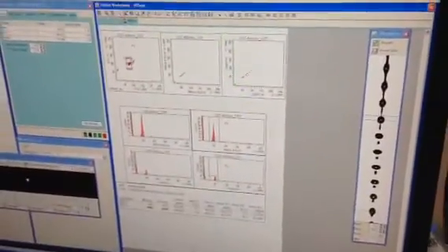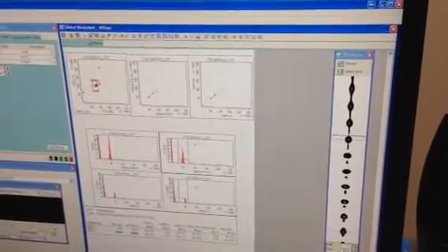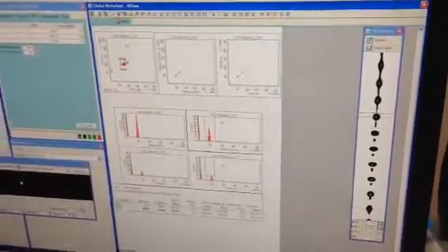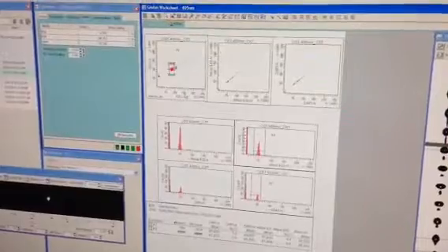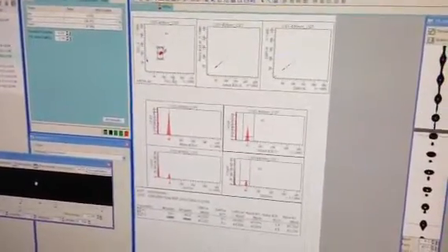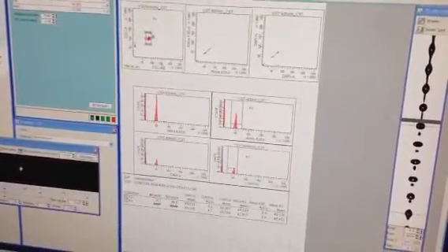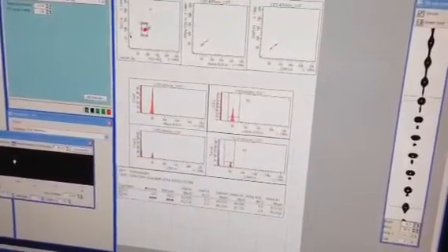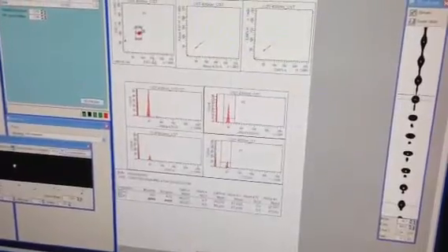So if the window extension is changed to 0, and we suddenly lose signal or the signal drops, we know that the laser delay is not set optimally for the bead or particle itself to be in the center of the window. So we would adjust our laser delay at this point to have the signal maximized at the 0 window extension, so that when we open up the window extension, we'll be seeing a complete signal very clearly and consistently. But by maximized, you mean at our target, which is 15? Yeah. Whatever we had previously set as our standard measuring point, we want that to be maintained every time. So it should not drop when you hit window extension 0. No, changing the window extension shouldn't cause that signal to drop if the particle is centered in the window. It did change on the forward scatter, but that's just expected.